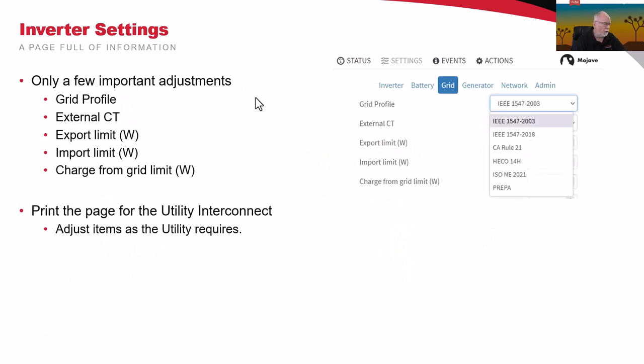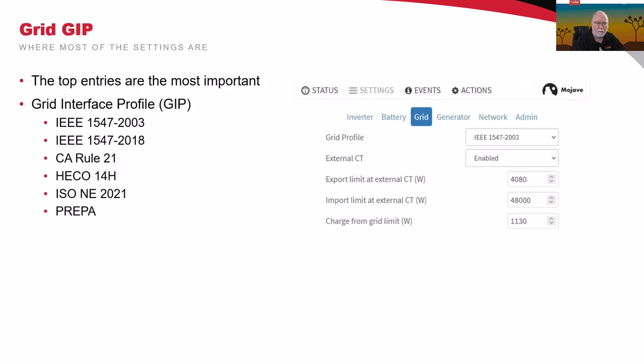Then, a couple of important items you have to do. So first, set up your grid profile. So go into settings, grid, select your grid profile. The other settings that are important underneath that are the external CTs, whether they're enabled or disabled, your import limit, your export limit, and your charge from grid limits. And you may have to adjust these based on what the utility requires.